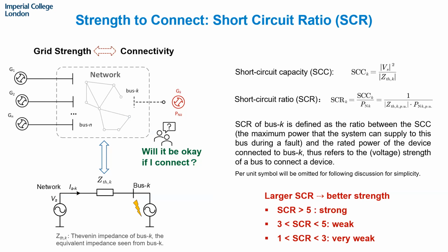To do that, we usually compute a Thevenin impedance of the network seen from bus K, which gives a voltage source in series with the Thevenin impedance. When considering a short circuit happening at that bus, we get the short circuit capacity, which is the power flowing from the network to that bus during the short circuit.